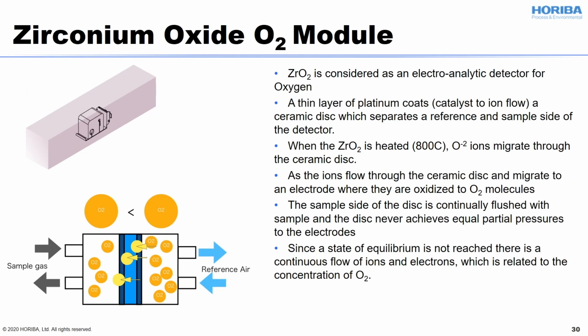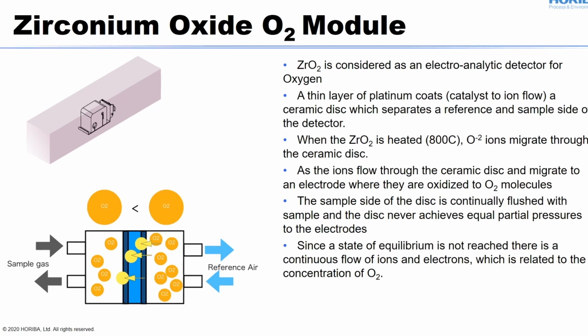Zirconium oxide O2 modules. Zirconium O2 is considered another electroanalytic detector for oxygen. A thin layer of platinum coats a ceramic disc. See this blue disc here, and when the zirconium O2 is heated to 800 degrees C, oxygen ions migrate through the ceramic disc. Ions flow through the ceramic disc from higher O2 concentration to lower concentration. Please see the picture here.